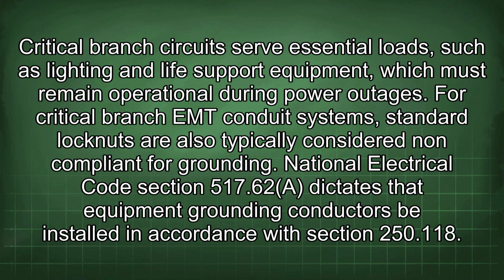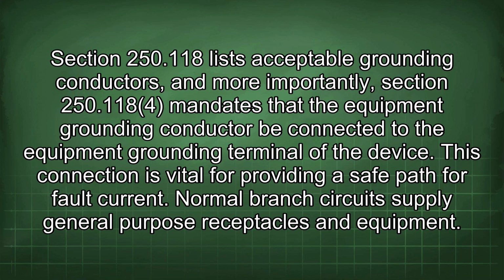Critical branch circuits serve essential loads such as lighting and life support equipment, which must remain operational during power outages. For critical branch EMT conduit systems, standard locknuts are also typically considered non-compliant for grounding. National Electrical Code Section 517.62 dictates that equipment grounding conductors be installed in accordance with Section 250.118. Section 250.118 lists acceptable grounding conductors, and more importantly, Section 250.118 mandates that the equipment grounding conductor be connected to the equipment grounding terminal of the device. This connection is vital for providing a safe path for fault current.